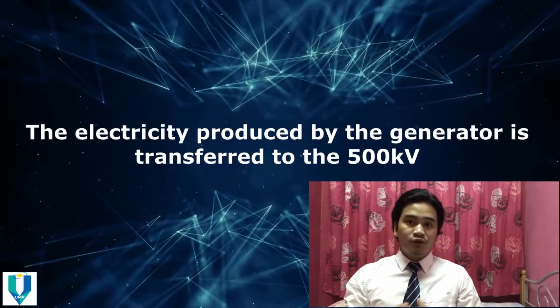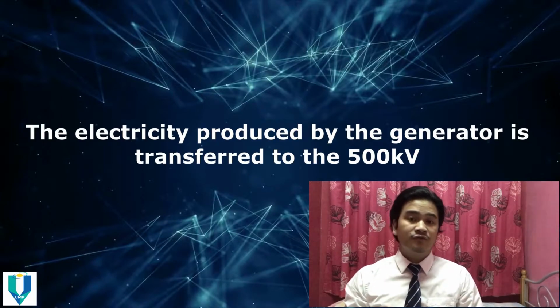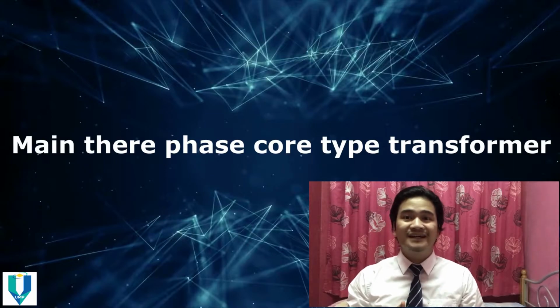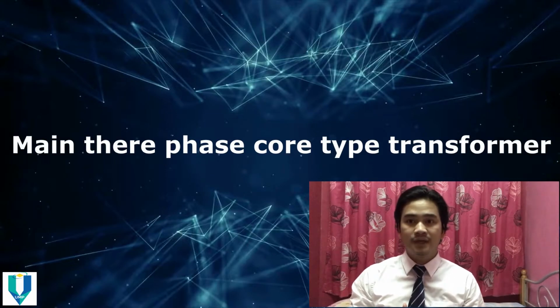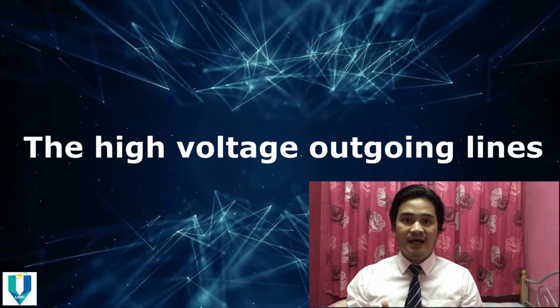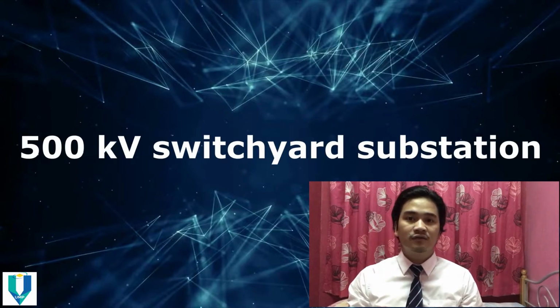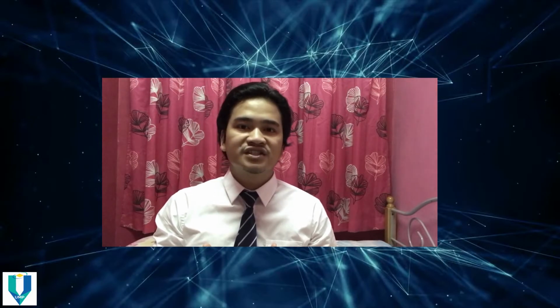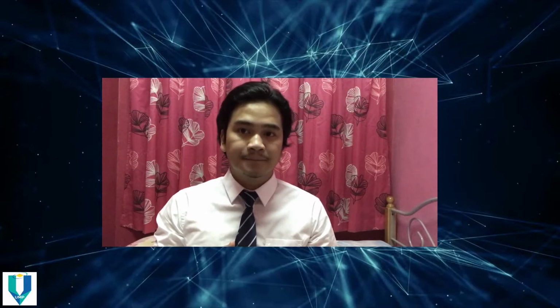The electricity produced by the generator is transferred to the 500 kV grid via main 3-phase core-type transformers. The high voltage outgoing lines are connected to the 500 kV switchyard substation. An isolated phase bus bar ensures the connection between the generator and the main transformer, as well as the tap connection to the unit transformers. In normal operation, the 11 kV network is supplied by the unit 3-phase transformer from the generator 23 kV bus bar.